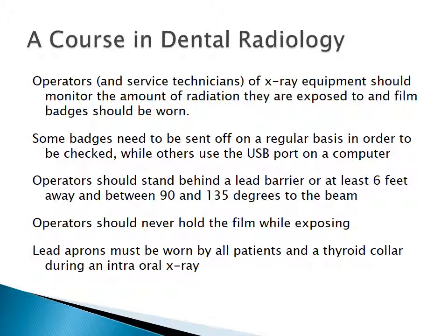So the operator themselves should always be standing behind a lead barrier at least 6 feet away, and put yourself at as great of an angle as possible. Obviously, you should never hold a film while exposing it, and you should always make sure that lead aprons and thyroid collars are being used on patients while they're getting X-rays taken.